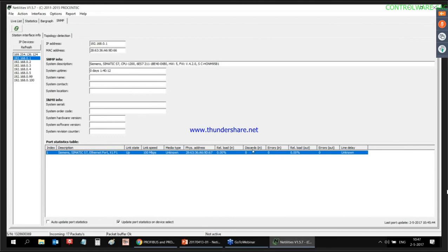You can imagine that if this controller is sending out and receiving a lot of packets, a lot of information, then the ports or the memory in the ports gets overloaded, and then it starts to discard messages because it just cannot handle so much traffic. So if there's traffic overload, then you will see discards here, and this is very useful information for troubleshooting.